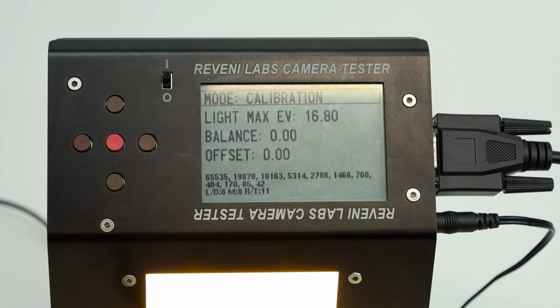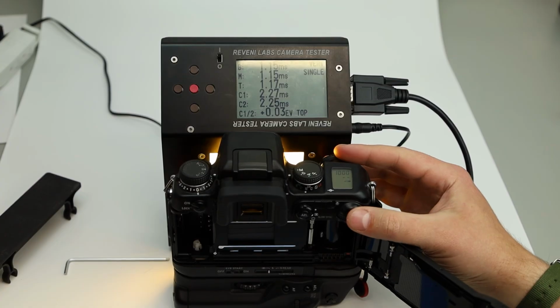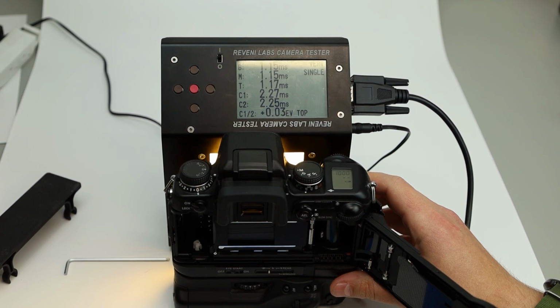After calibration is finished, make sure that the balance and offset values that are shown in the calibration page on the menu are set to 0. They may default to some other number because of the previous firmware having already been on this unit. And so just make sure that they're set to 0.0. I'm going to demonstrate the process for setting the balance on the sensor.